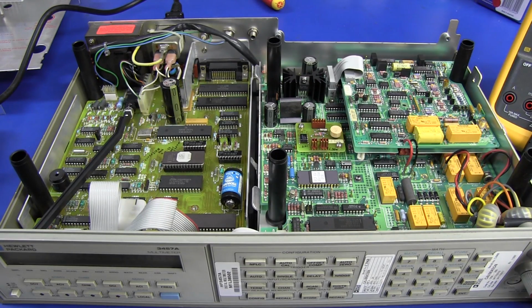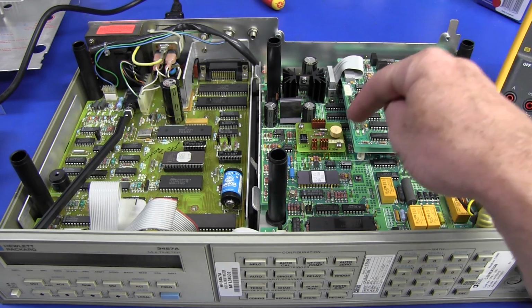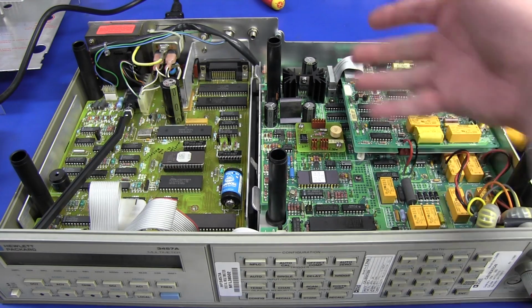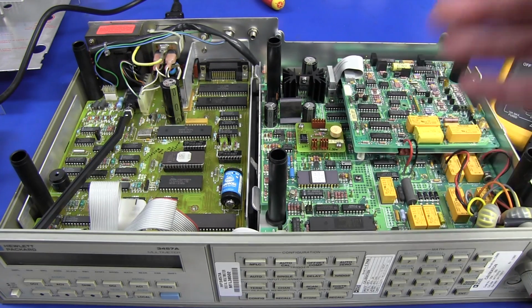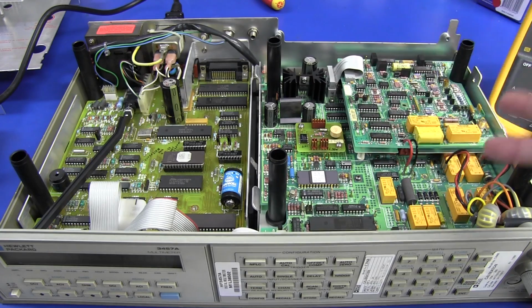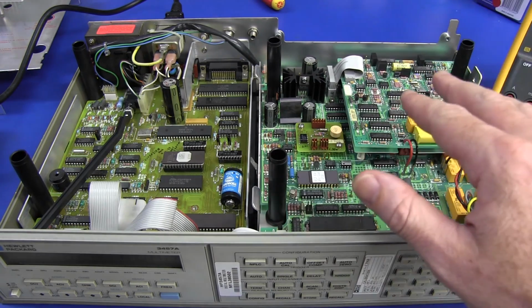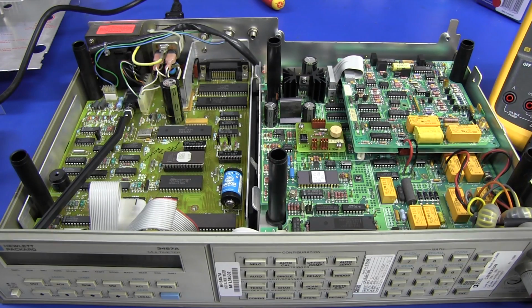And you don't want thermal gradients, because if you've seen my thermocouple video, you'll know that basically any dissimilar metal junction within this unit, any junction at all, solder and copper clad board and everything else, creates dissimilar metal junctions acting as a thermocouple. So you're going to get EMF voltages generated in the unit. So the last thing you want in something like this, you would rather have it heat up to a warm temperature and stay nice and even than try and cool it down with airflow through the thing. And we can demonstrate this.